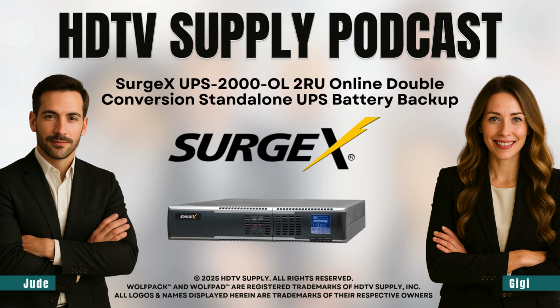How so? It's always online. It takes the utility power, rectifies it from AC to DC, and then regenerates a completely new pure AC signal. So my equipment is never actually touching the grid power directly. Never—it's always running off the UPS's own perfect clean power. That's what they mean by network-grade power.